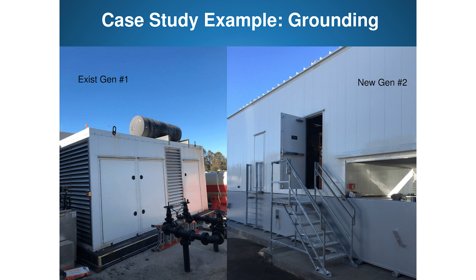In this project there were two generators. There was a generator, and then they were going to put another one in there, which is fine, that happens all the time. But when you're adding new generators and transfer switches to existing generators and transfer switches, it's very important that we make sure the grounding systems are appropriate, and the transfer switch types, whether they're 3-pole or 4-pole, are appropriate for the type of grounding.